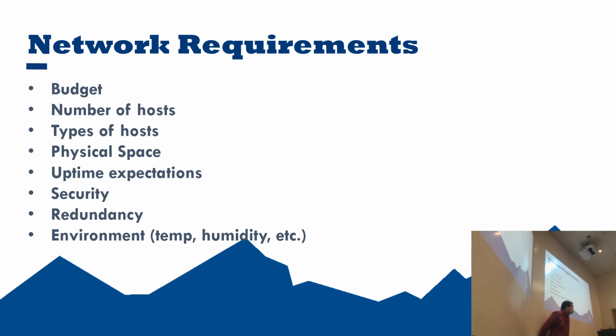I'm sure you guys have had some humidity days where you walk outside, you get sticky, you get a lot of sweat build up. Now imagine you have condensing humidity in a server room. You're going to have condensation form inside your equipment. Do you think that's going to be good or bad for the equipment? It's going to be very bad for the equipment. Most things are rated between 5% and 95%, but not everything is rated for 95%. And beyond that, let's say it's condensing humidity, you could certainly void a warranty that way, be out thousands of dollars.